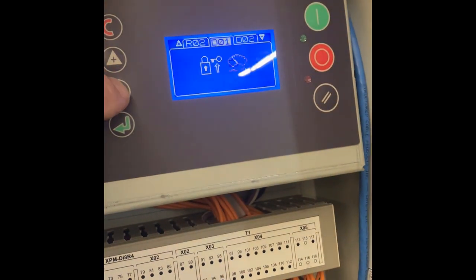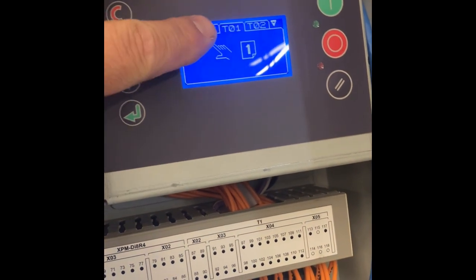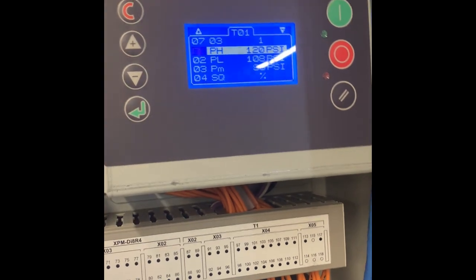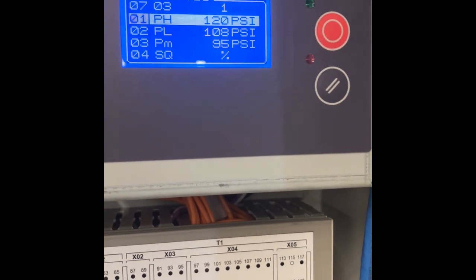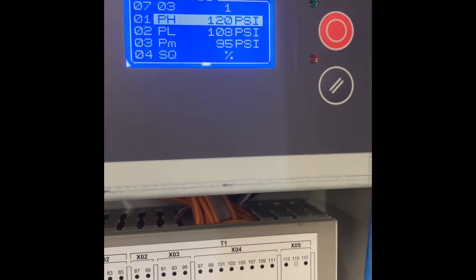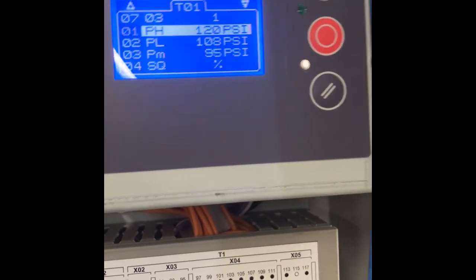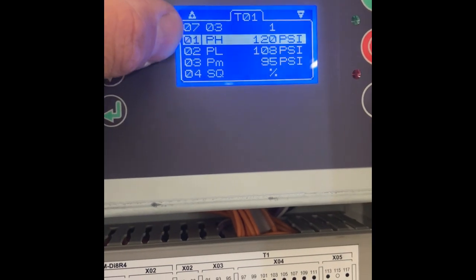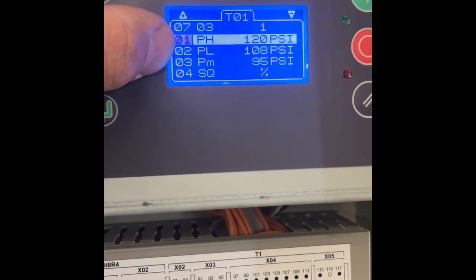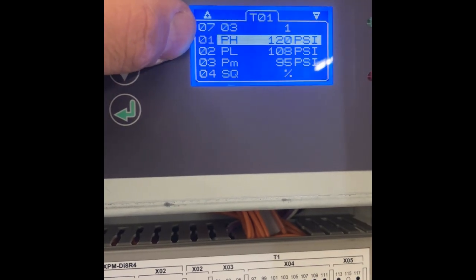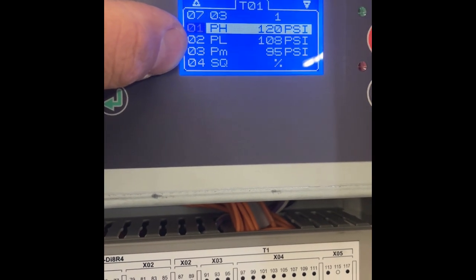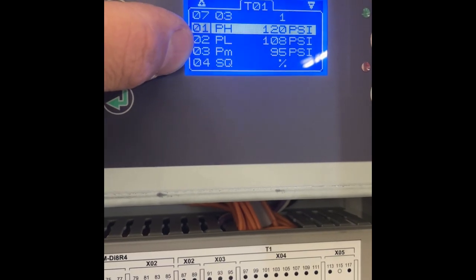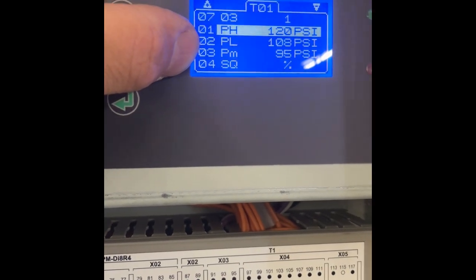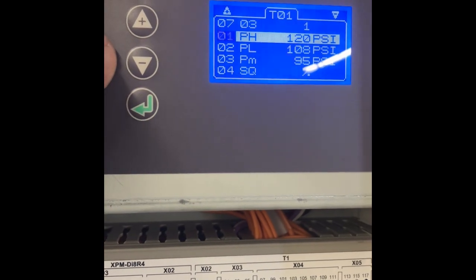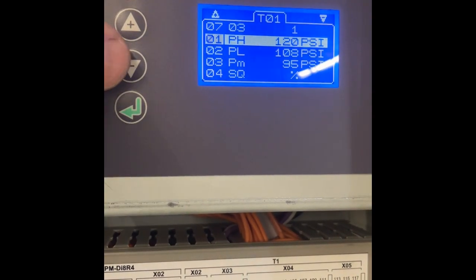So then if we go to table 1, which is our default pressure table, this is where we set high and low pressure, and our pressure minimum. My high point's 120, my low point's 108. The Aero is going to try and maintain about the middle of that. My pressure minimum, which is kind of my oh-crap pressure, is 95 psi. So if pressure gets down to 95 psi, it's just going to start calling for machines and trying to make air. It's not going to be too worried about efficiency at that point.